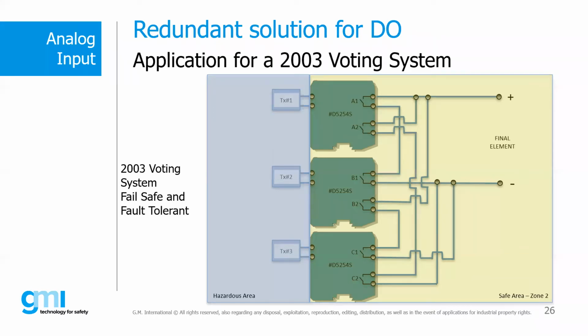In fact, when at least 2 out of 3 sensors detect the same variable in the field, the related trip amplifier will activate its contacts, and consequently the final element is activated. If one of the elements in the field fails, or if one of the trip amplifiers fails, the 2 out of 3 redundancy allows us to maintain our safety function and process availability at a high level.